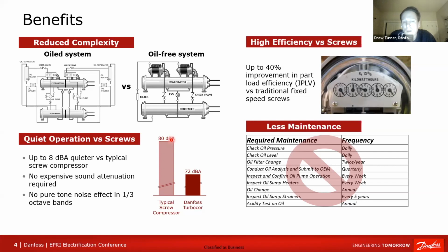And so the result is something that is significantly quieter than everything else that's out there today. If you have no contact, you just primarily have the noise of the refrigerant going through the compression process. And so that ends up meaning about 8 dB quieter than an equivalent capacity screw compressor. If you know noise, that's a logarithmic scale, and so every 3 dB reduction is about a 50% reduction.